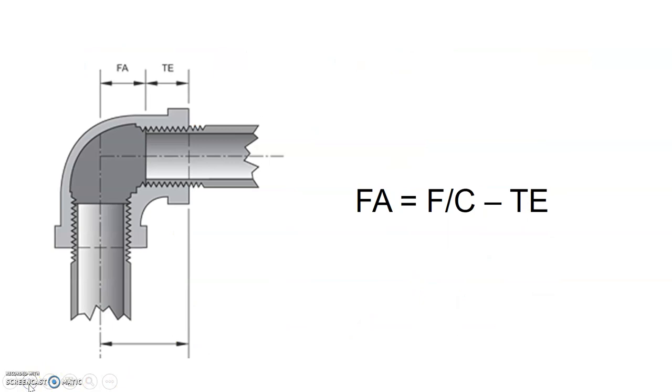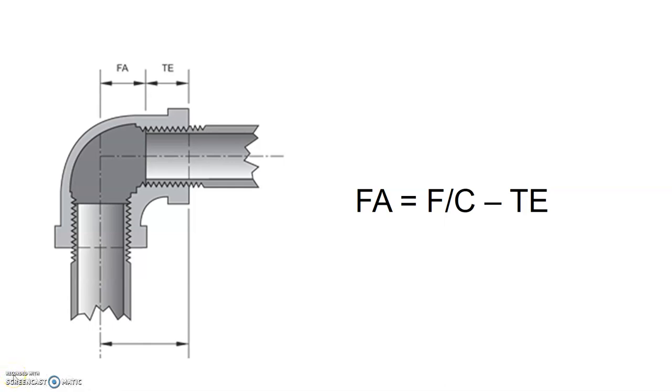Once we have done that, we've got the face to center. We take the face to center and we subtract our thread engagement that came out of the American Pipe Thread Data table. Our face to center was our measurement that we either measured ourself physically by measuring from the face to the center of the other outlet, or we got off a manufacturer's table. So we take our face to center, we subtract our thread engagement, that will give us our FA, otherwise known as our fitting allowance.